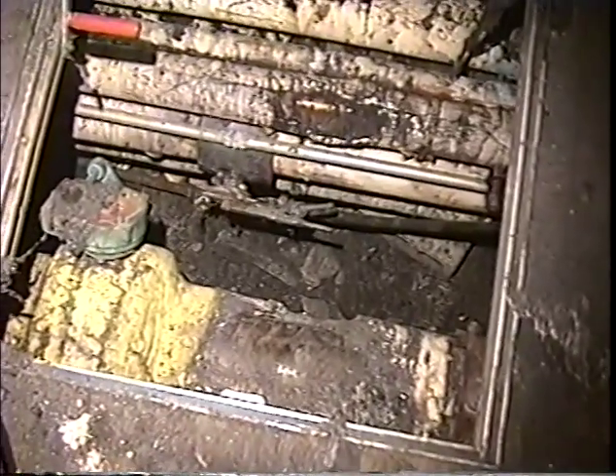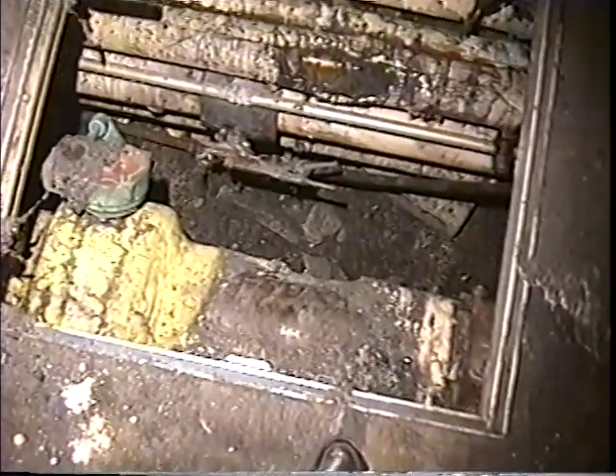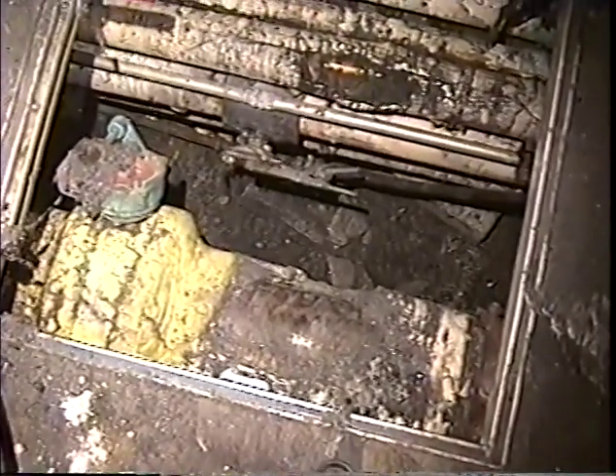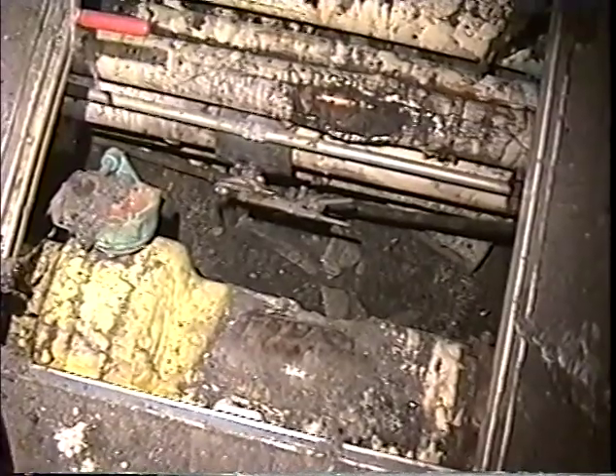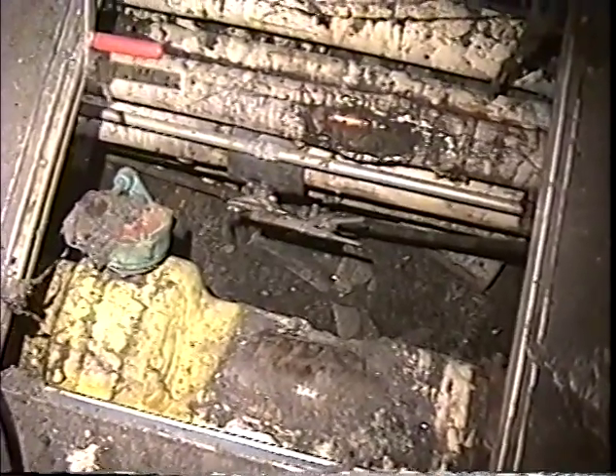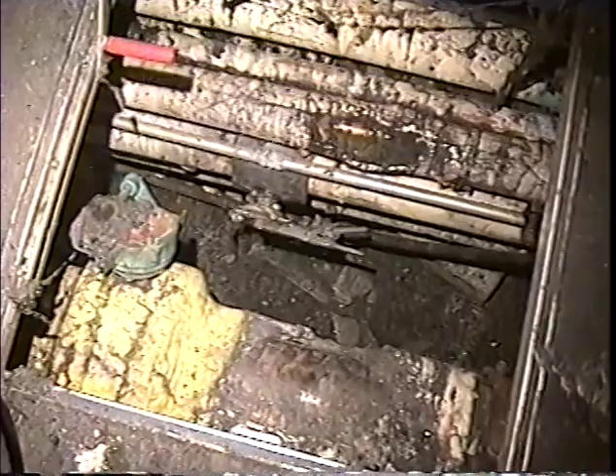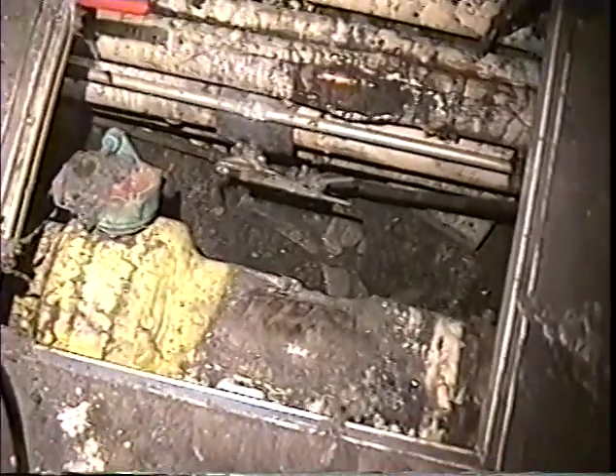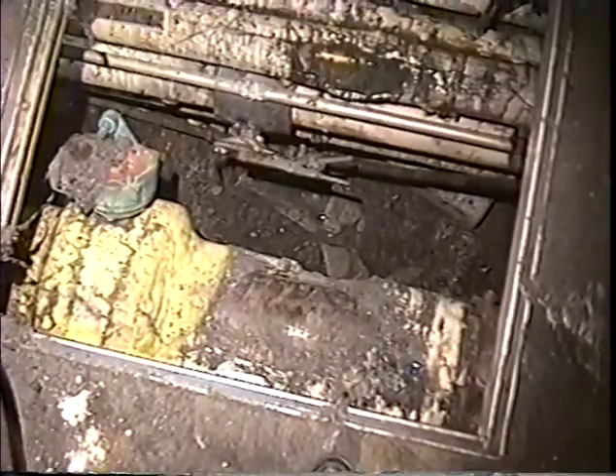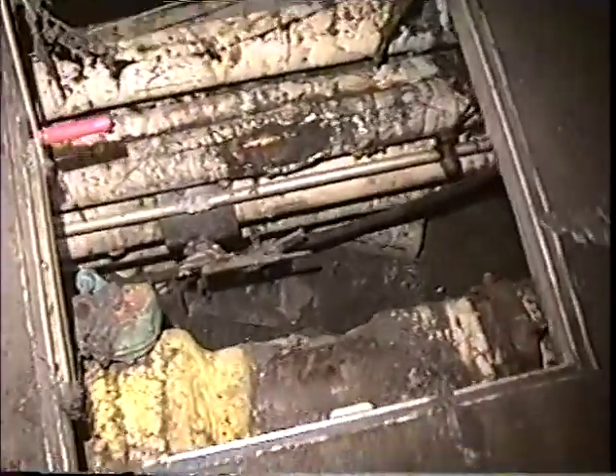Anything down in there of significance? Nothing of any significance down there. This was used to wash the floor, and a lot of our floor washing water went down this tunnel. And the damage to the pipe insulation we feel is from maintenance people getting down in the tunnelway and using that for handholds and step area, rather than fire extension.